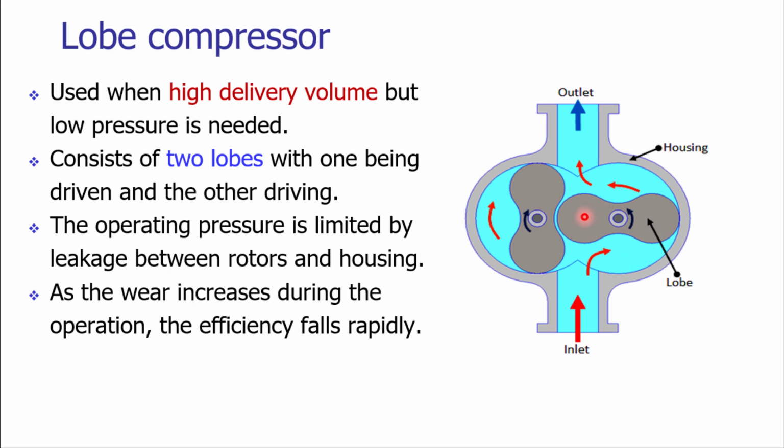The lobes are pressurizing, carrying, and pushing the fluid inside the gap. As the volume of the gap is reduced, there is an increase in the pressure on the fluid, that is the air or the gas. As the lobes move further, that compressed gas or fluid will be pushed out through the outlet.